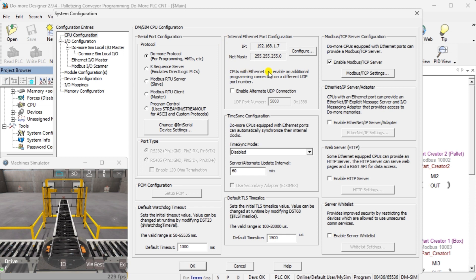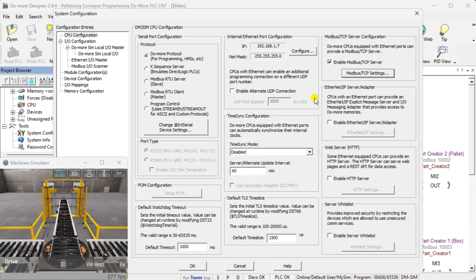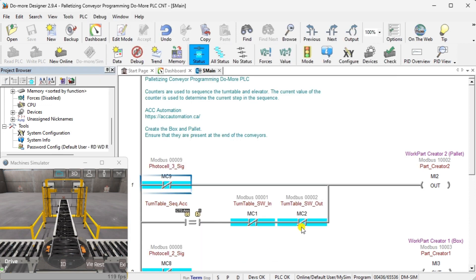This address can be seen under the heading Internal Ethernet Port Configuration. You can also click on the menu button. Ensure that the Enable Modbus TCP Server is selected. Click the Modbus TCP Settings button. We will leave the default port of 502 for our Modbus communication. Our DoMore PLC is now a Modbus TCP server to the Easy PLC Modbus TCP client. Note the IP address we are using for the DoMore PLC simulator, as this will be used later to connect the Easy PLC machine simulator.